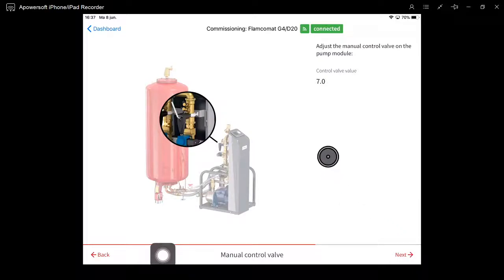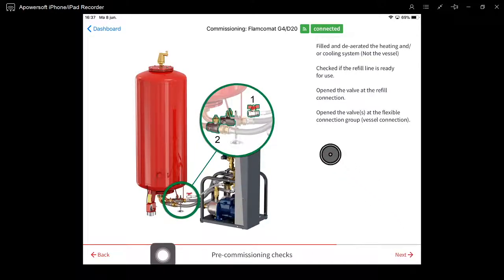Then I have to adjust this valve here. That's the manual control valve on the pump module. And I have to put in the figure 7.0. I can do that with an Allen key, by turning that Allen key until I can see here in the display of the valve 7.0. After doing that, I can press next again.